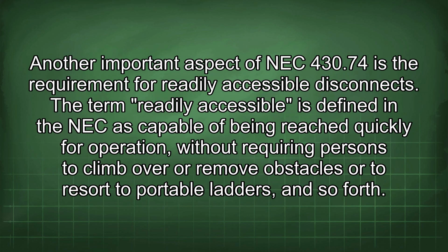Another important aspect of NEC 430.74 is the requirement for readily accessible disconnects. The term readily accessible is defined in the NEC as capable of being reached quickly for operation, without requiring persons to climb over or remove obstacles or to resort to portable ladders, and so forth.